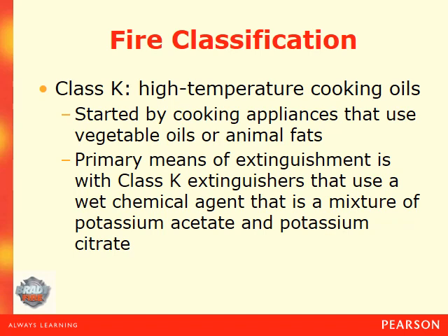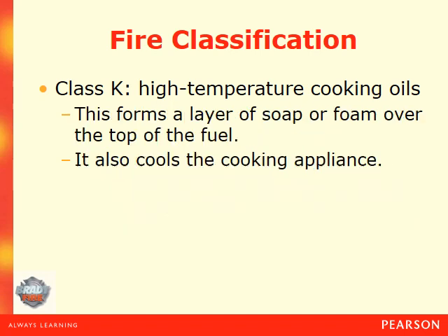Finally, you have the Class K fire, and that's relatively new in terms of the classification compared to the other ones, and that's basically your cooking oils. They decided to break it off from your flammable liquids and make its own separate category because it has some very unique features. With your Class K or oil fires, you can add certain extinguishing agents and turn it into an emulsifier, basically like a soap form, to put the fire out.